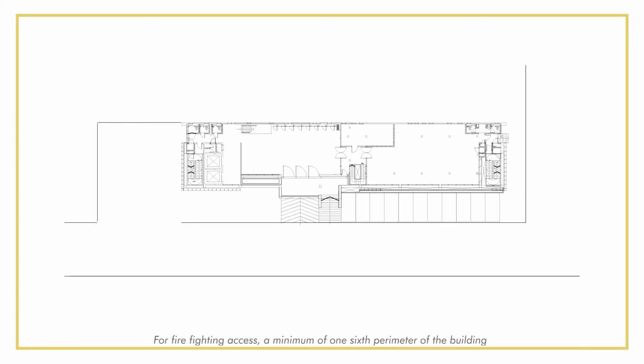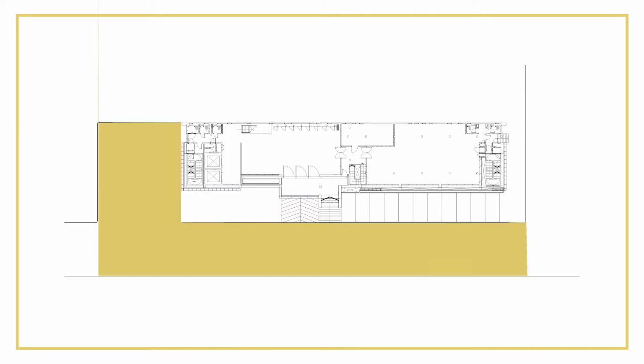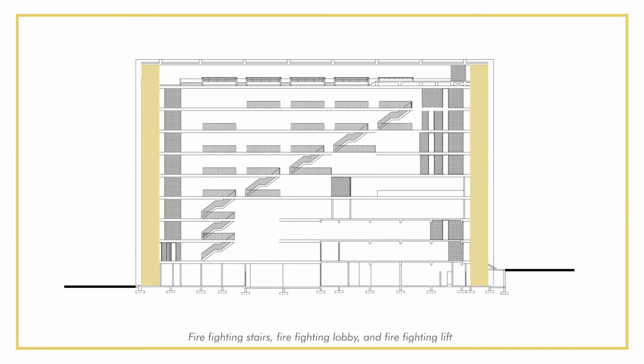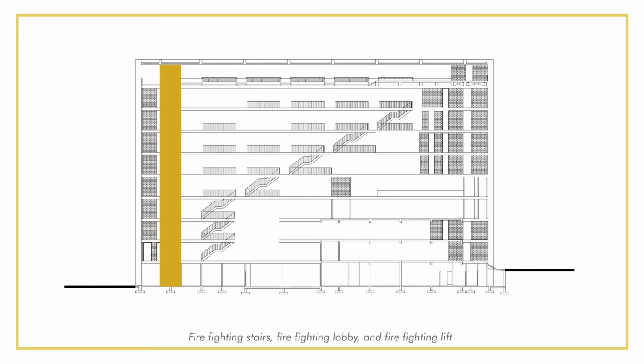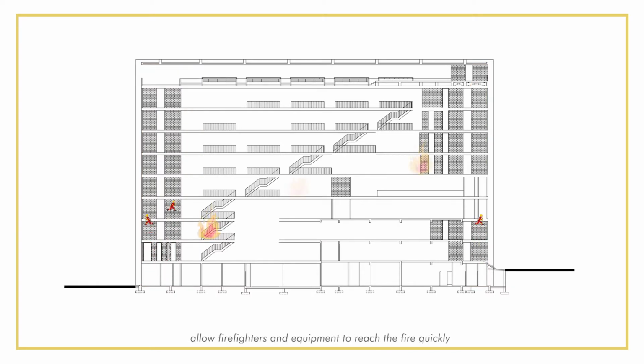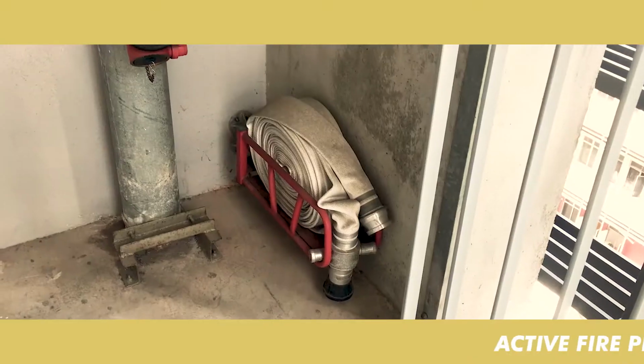For firefighting access, a minimum of one sixth of the perimeter of the building should be provided with a fire appliance access road. The main road in front of the building is sufficient to fulfill the requirement. Firefighting stairs, firefighting lobby, and firefighting lift allow firefighters and equipment to reach the fire quickly.